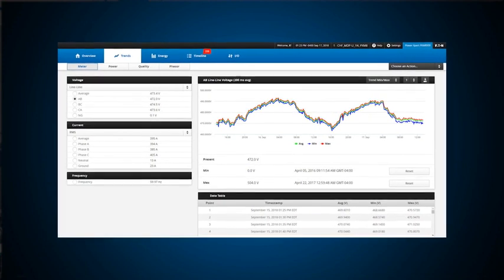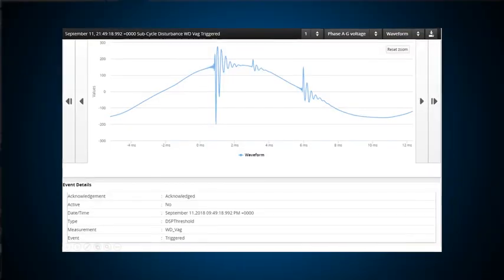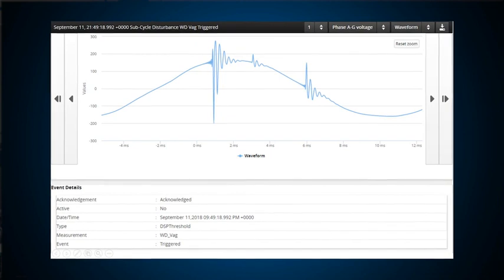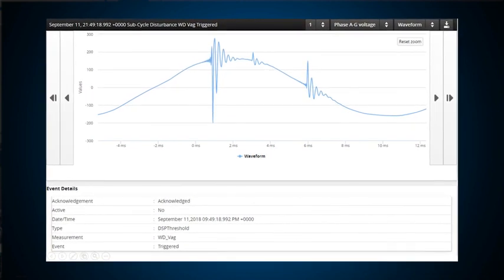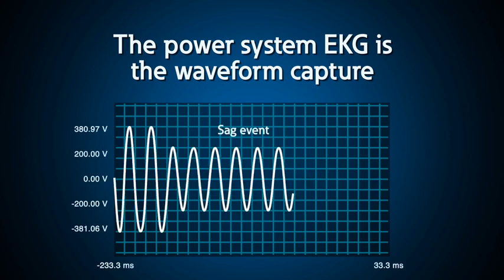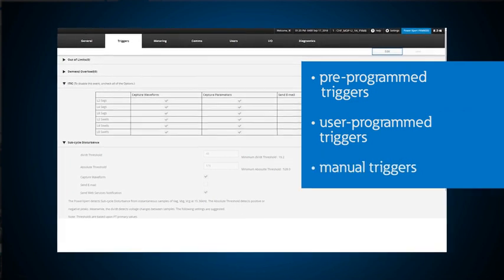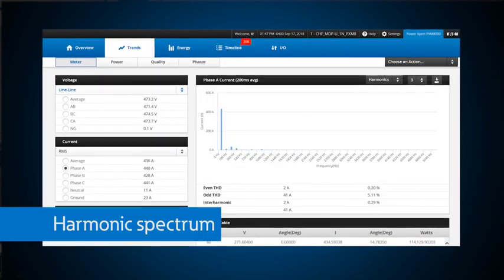For basic analysis, let's start off by looking at the metering page. The power expert meter captures all the important signals including voltage, current, and power parameters thousands of times every cycle. This means it can capture transient events that exist only for nanoseconds, but can also intelligently process such a large quantity of data to find the transient anomalies. The EKG of the power system is the waveform capture. Waveforms can be triggered from pre-programmed or user-programmed events, or you can take a manual snapshot of the waveforms for voltage and current, as well as the phasor diagrams and harmonic spectrum.